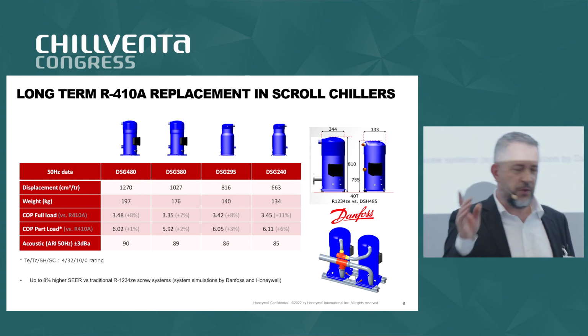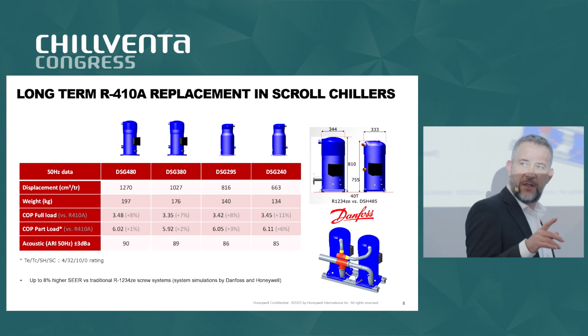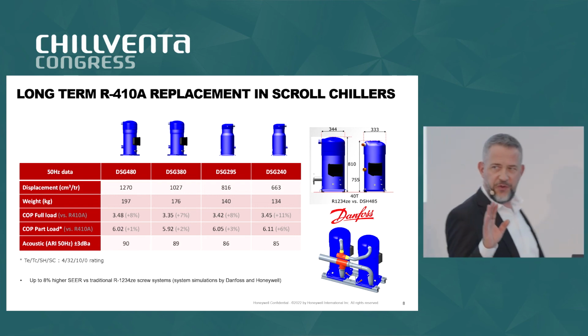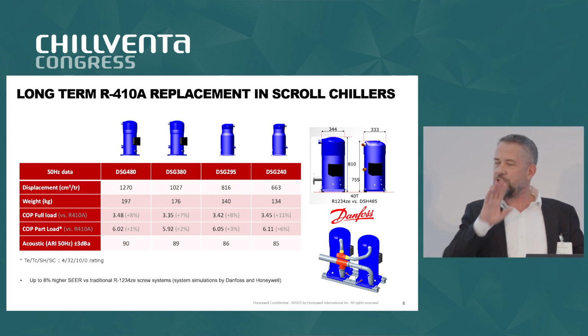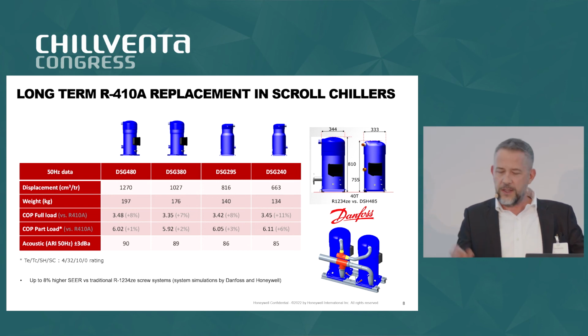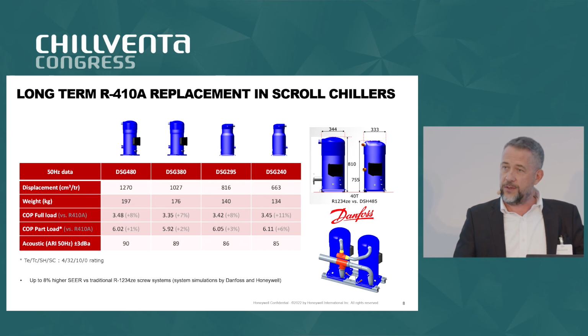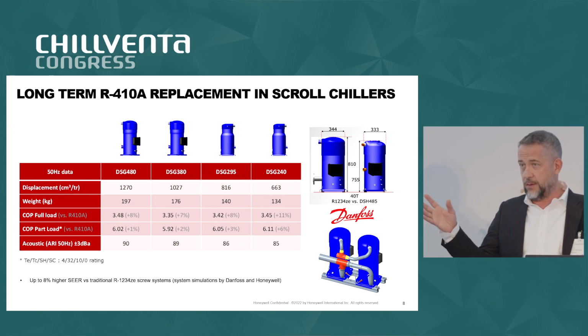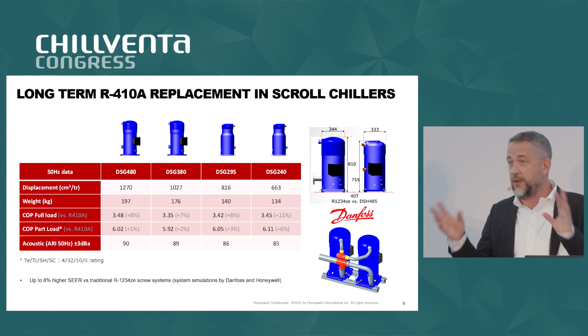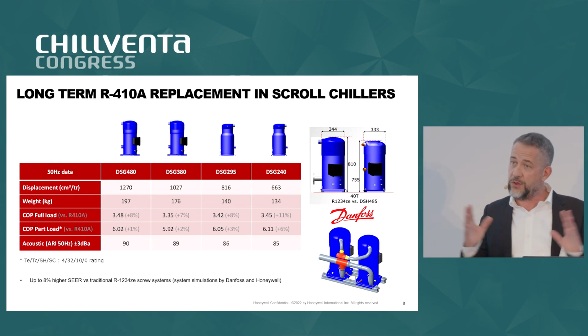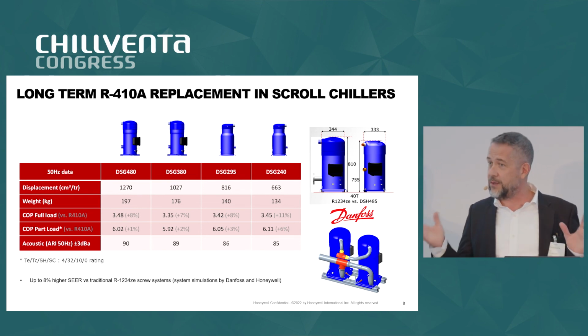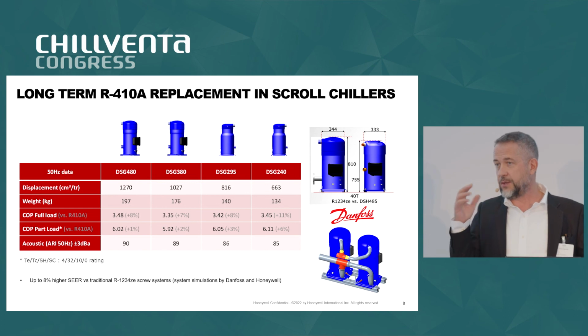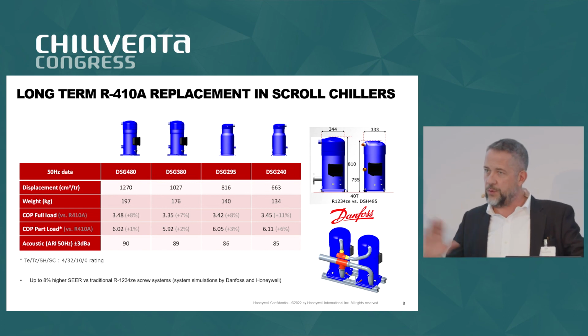No, this isn't about refilling a 410A unit or retrofitting, just new systems. You cannot retrofit a system based on A1 with A2L or A3, because you lose all the CE marking and guarantees around that. So no, this is only for new build, new business, new chillers.